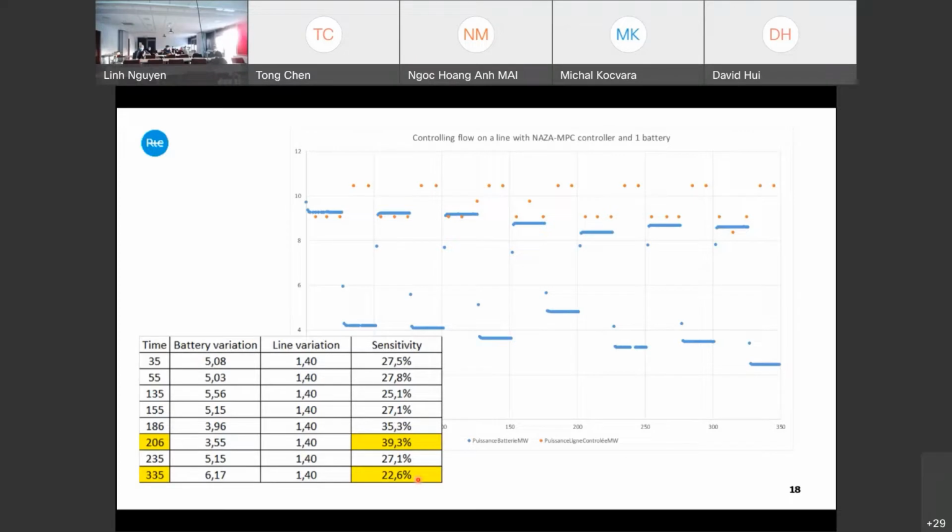This was measured. This comes from tests made in November, and this was really unexpected. So we will have to fix this. And here the problem is that the measurements are discrete. The discretization here is 0.7 megawatts. We will do further testing to identify this problem. But have in mind how to handle this in some optimization model.